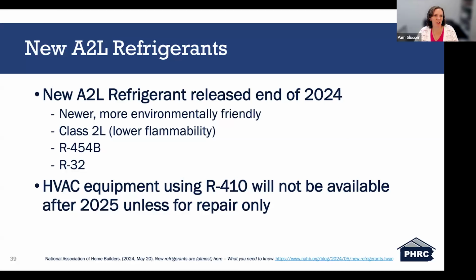So talking about installation, the new A2L refrigerants, as of the end of 2024, HVAC equipment is no longer being made using the R410 refrigerant. All equipment is now being manufactured using the new A2L refrigerants.